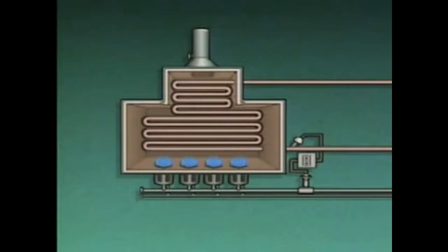When you shut off fuel to some of the burners, the fuel flow to the operating burners will be increased, reducing the risk of flameouts. Firing with fewer burners is a way of maintaining fuel pressure while satisfying the reduced demand.